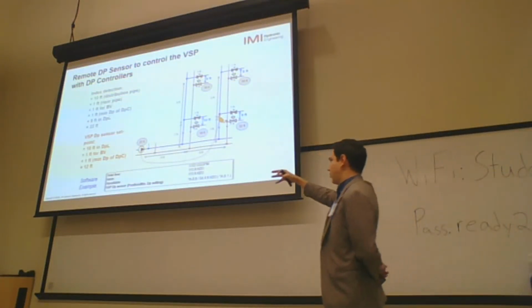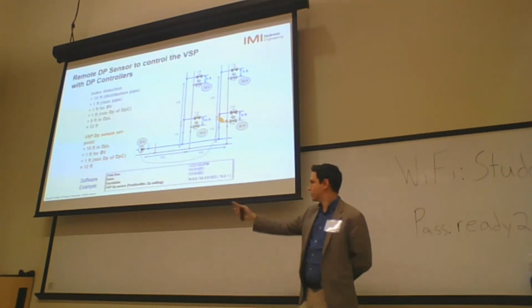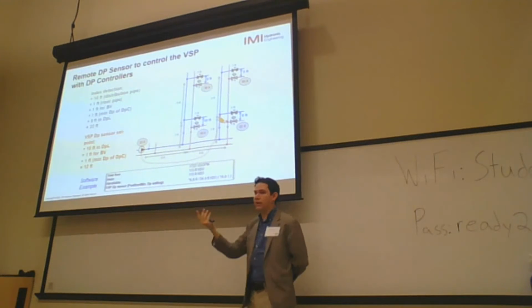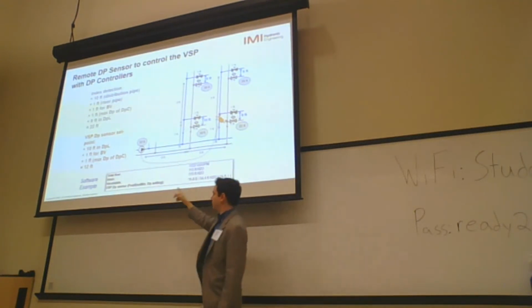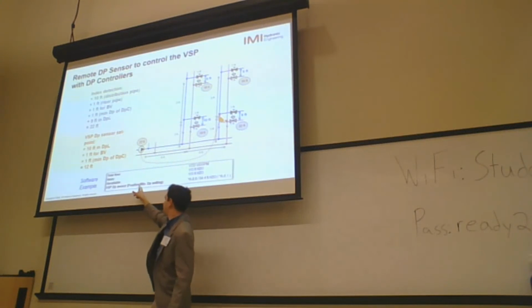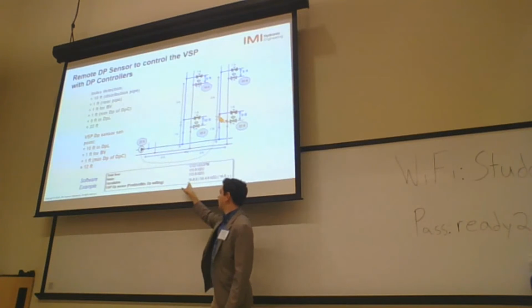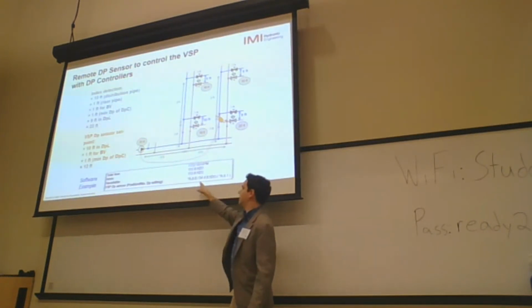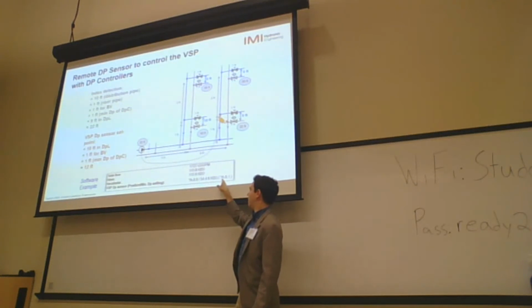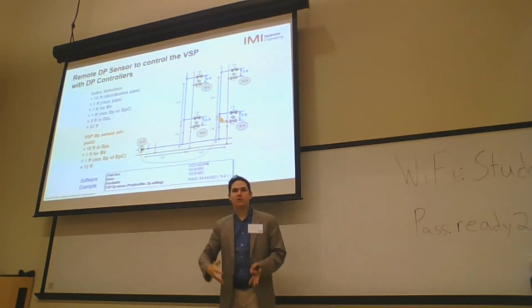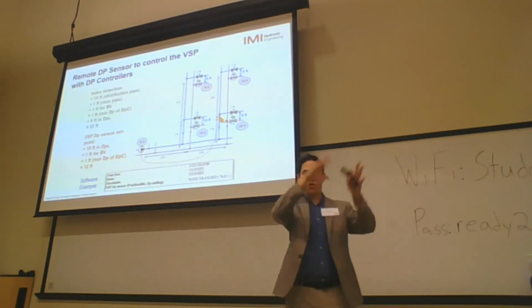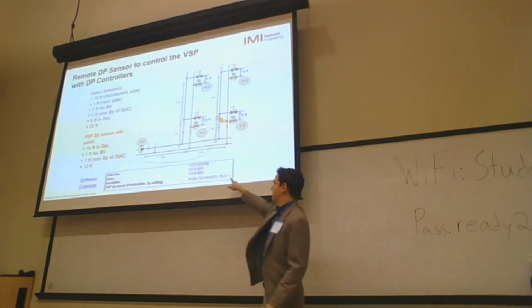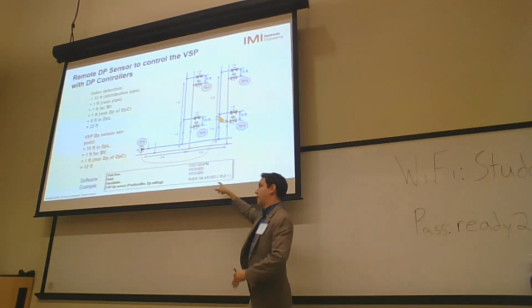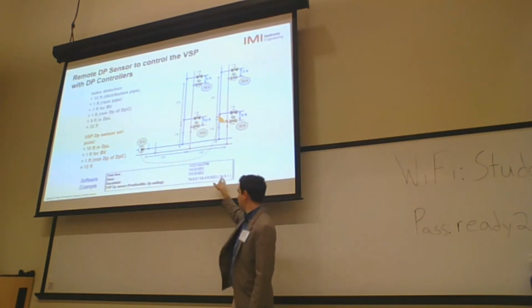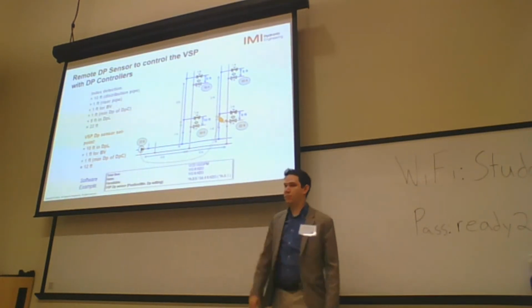This is just a simple example with easy numbers to run the calculation. Of course, there is software that can calculate that easily for the whole installation. So here is the variable speed pump, DP sensor, position, and minimum DP setting. The position is the name of the branch. And the set point is 54.4 because it is branch A61. That is the branch with the highest pressure drop inside the branch. Not overall, but inside the branch, this one has the highest required pressure drop for the installation. That is 54.4. That is the set point for this DP sensor in this example.